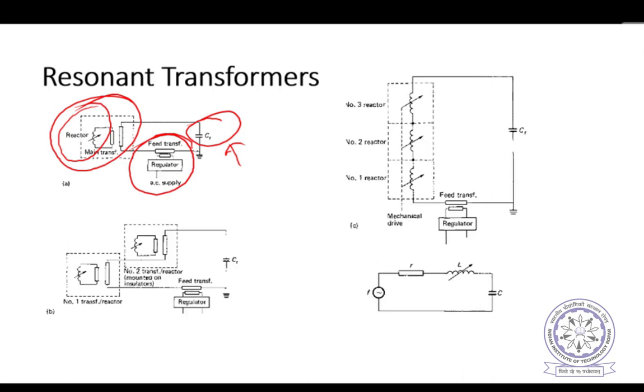To achieve the resonance condition, under resonance condition high voltage will be applied here, and after achieving the resonance condition, again a regulator transformer is used, and slowly whatever required voltage will be achieved by changing the regulating transformer voltage. So this is how high voltage AC is generated in a laboratory using the resonance principle. Now similarly, 3 reactors can be cascaded like this, or 2 reactors here can be cascaded. This is another principle, actually.